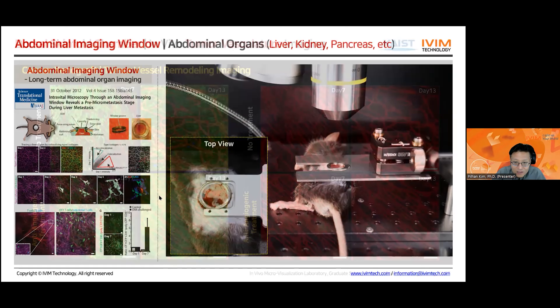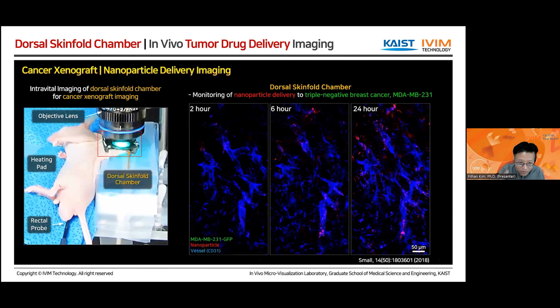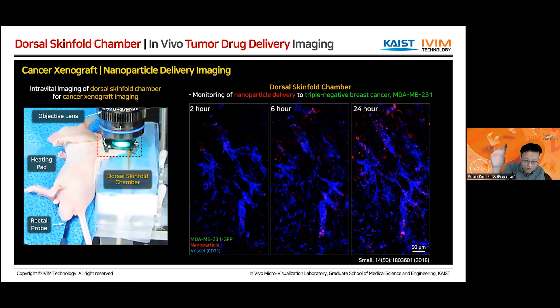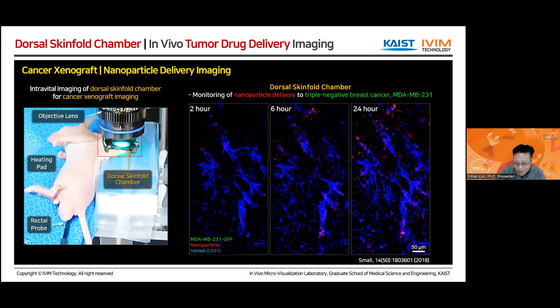Moving the lens is another story — what we can do is multi-position imaging. Our stage is motorized and we can program the stage to move around multiple positions repeatedly with a time interval. For example, we observe five different locations with a one-minute interval — take an image at one spot, move to another spot, take an image, and so on, doing this at five different locations and then coming back to the first spot. That's how we extend our imaging field of view, and it's automated with our stage.